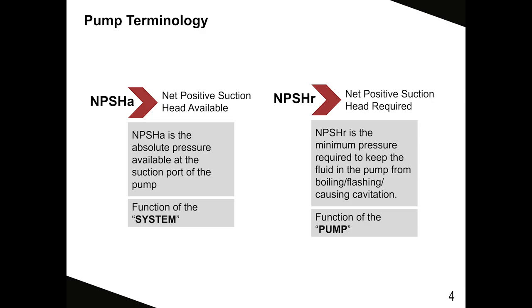Unlike chilled or hot water systems, which are pressurized by expansion tanks, fuel oil systems typically operate in a vacuum on the suction side of the pump. For this reason, NPSH is critical. NPSHA, net positive suction head available, is a function of the system. You, as designers, have influence on this based on elevation changes, pipe routing, and sizing and number of fittings.